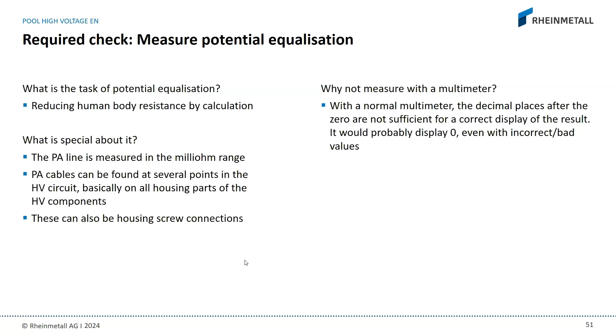I did a calculation to show you how this potential equalization works. On the left side, I was measuring the potential difference with 0.001 ohm, so 1 milliohm. The result, if I put a 500 volt battery on it and create a short, which will be a human body, is 13 milliamperes, 0.013 amperes, going through the human body. The rest of the energy goes through the battery, and there is a fuse which breaks down.